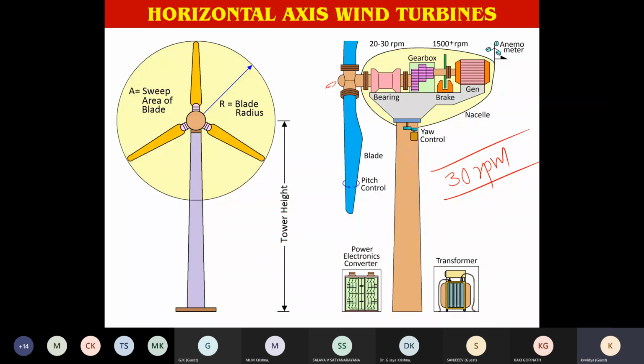It's very difficult. Of course, we can generate it using N equals 120 f by P. So with a 30 RPM turbine, we need a generator with 200 poles. A generator with 200 poles standing at a height of about 100 to 120 meters from the ground is practically very difficult. Of course, that is a very low speed.